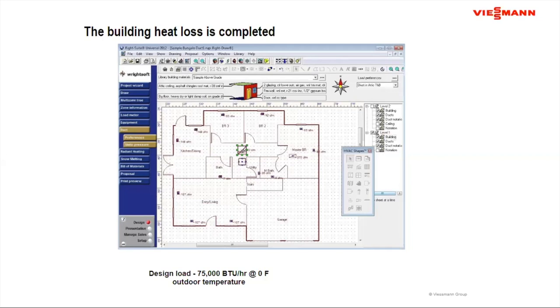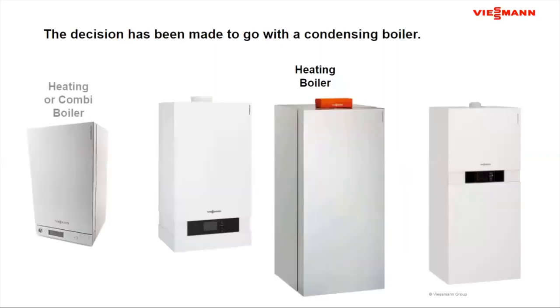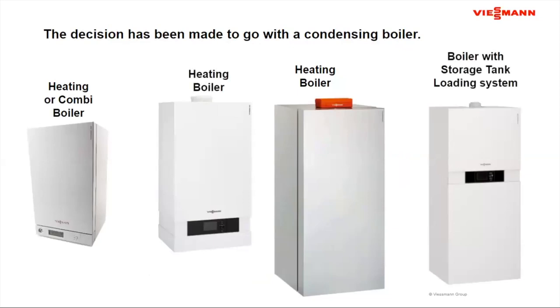This happens to be right off a software package I've used in the past. And let's call the heat load of the building 75,000 BTUs per hour. So that's one of the numbers we're going to have to look at when we look at the domestic hot water loading of the system. Now, the decision is already made to go with a condensing boiler. We haven't made the decision on which style of condensing boiler, but we know that we're going in that direction.